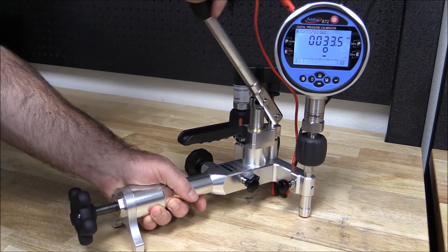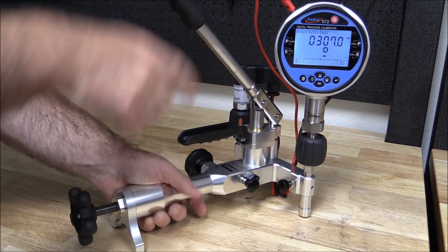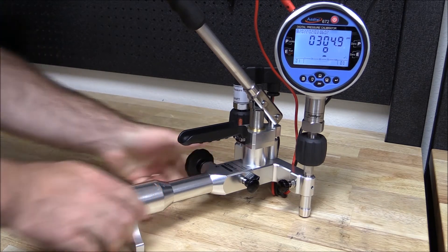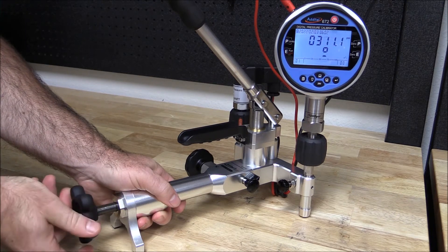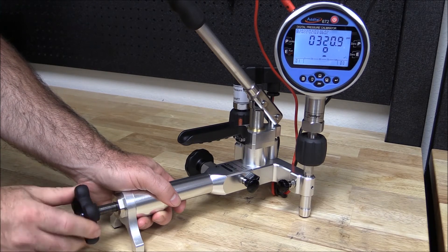With Additel pneumatic pumps, pressure can simply be generated with the hand pump. As we approach the set point pressure, we can close the isolation valve and use the screw press for fine adjustment. With Additel's unique pump design, the isolation valve isolates the calibration volume from the hand pump and the check valve, providing more stable measurements than traditional hand pumps.